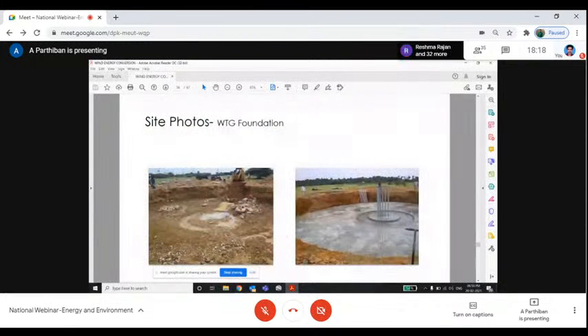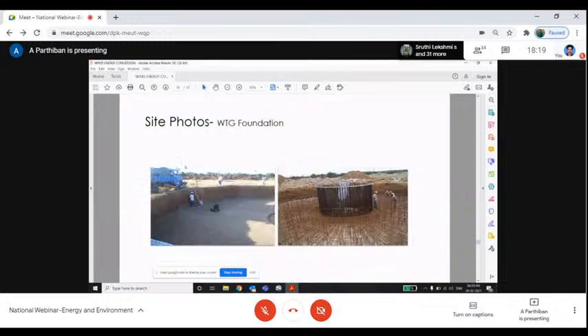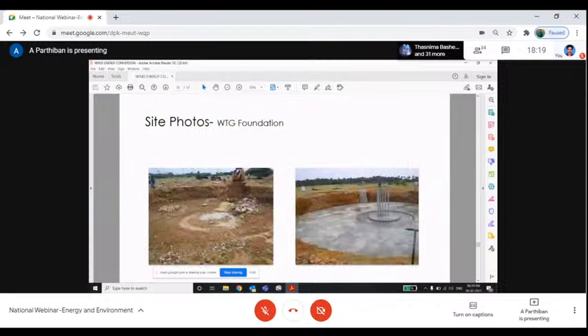start excavation. For example, what we have shown is a 2 megawatt turbine. It is a 20 meter diameter and 2 meter depth. We need to excavate the ground for 20 meter diameter with a 2 meter depth, and we need to have a sand bedding, because that will have a cushion impact for the total tonnage. Because if you see the total WTG, it will be around 250 to 300 metric ton, which will sit on that sand bedding.